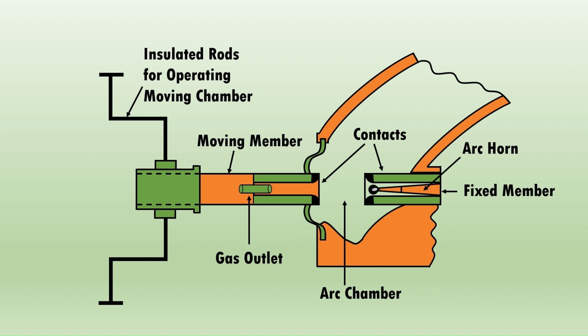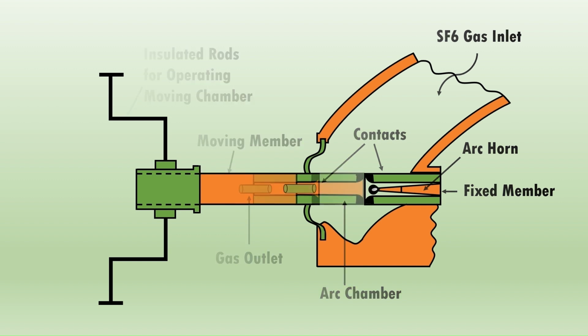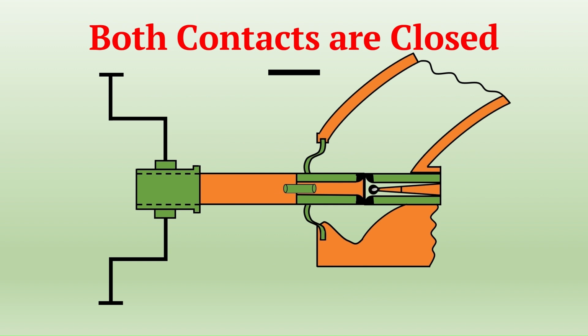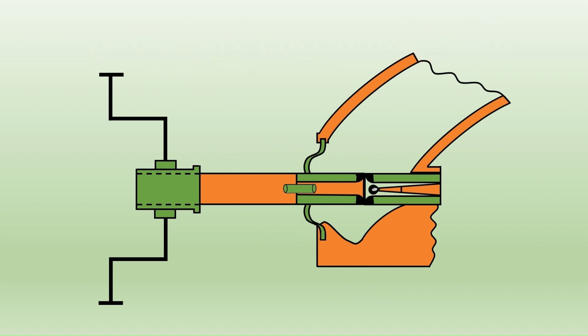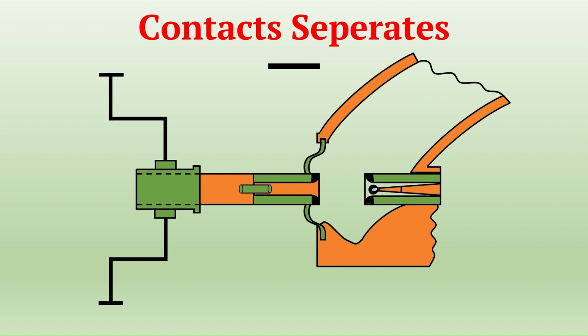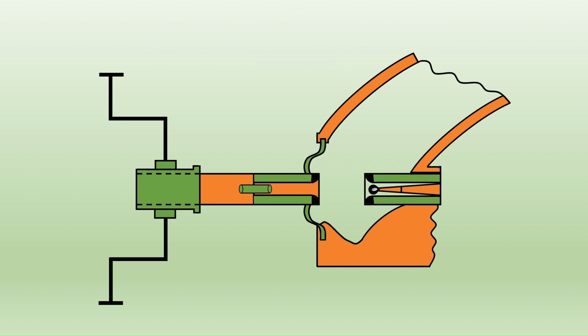It means as soon as the moving contact separates from the fixed contact during any fault, the valve of the SF6 gas tank will automatically open and gas will flow into the arc chamber. Initially, the contacts are in closed position surrounded by sulfur hexafluoride gas. When there is a fault in the system, the moving contact begins to separate from the fixed contact. According to the arc interruption theory, the surrounding medium will ionize and an arc will be struck between the contacts.